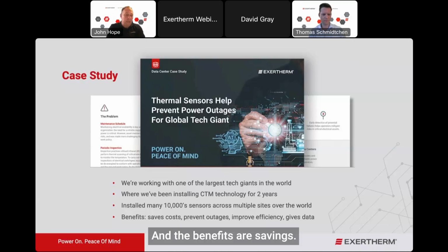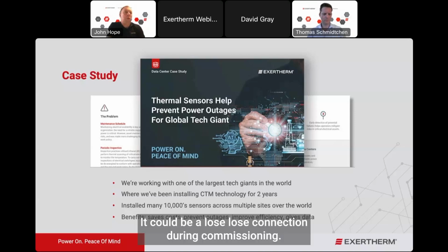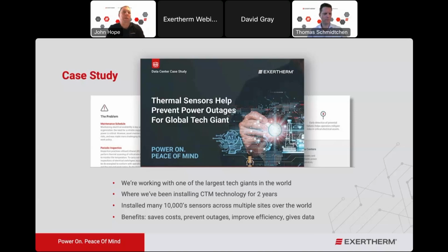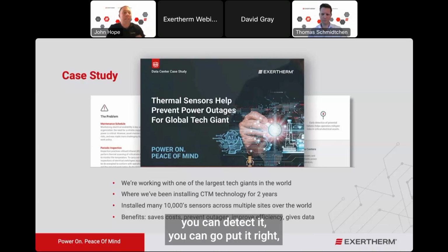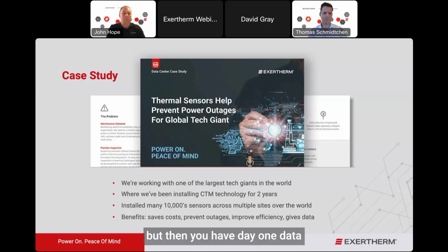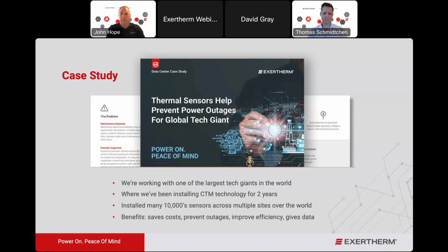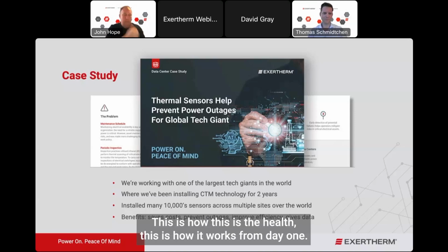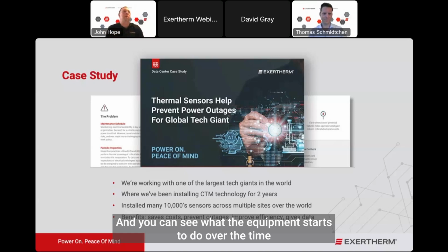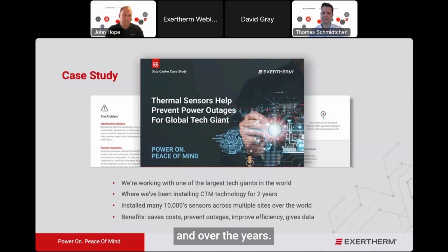And the benefits are savings, we're preventing outages, it's improving efficiency, it's giving data, and that's data from day one, even at commissioning stage. You've now got data that can alert you there could be a loose connection during commissioning. You can catch that. You can detect it. You can go put it right. But then you have day one data for all your equipment going forward. This is the health. This is how it was from day one. And you can see what that equipment starts to do over the time and over the years.